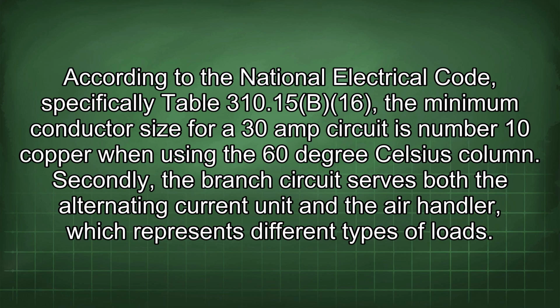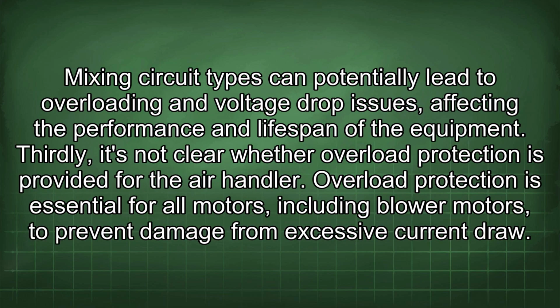Secondly, the branch circuit serves both the alternating current unit and the air handler, which represents different types of loads. Mixing circuit types can potentially lead to overloading and voltage drop issues affecting the performance and lifespan of the equipment. Thirdly, it's not clear whether overload protection is provided for the air handler. Overload protection is essential for all motors, including blower motors, to prevent damage from excessive current draw.